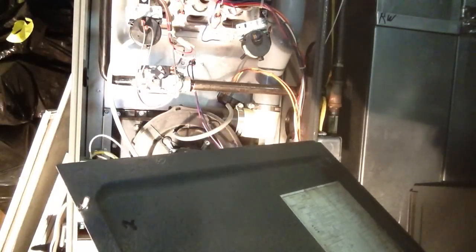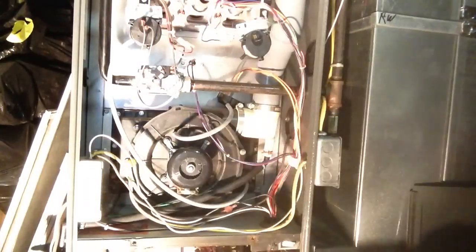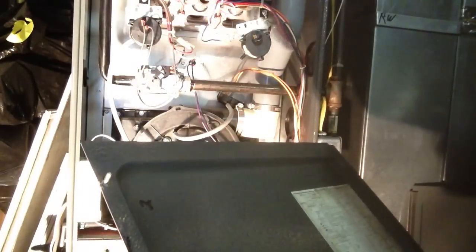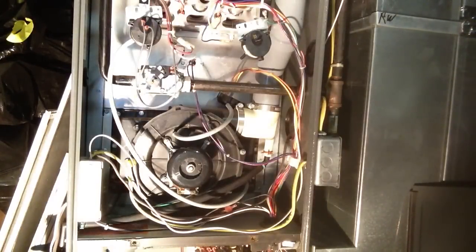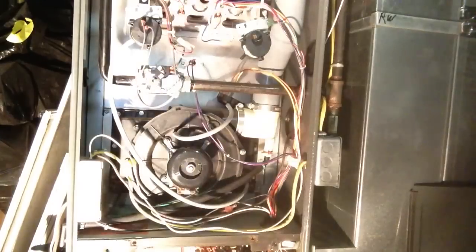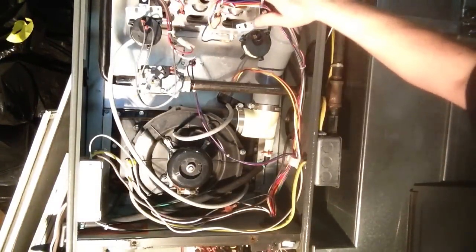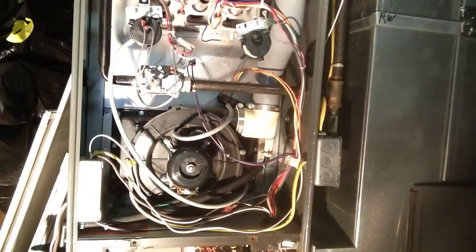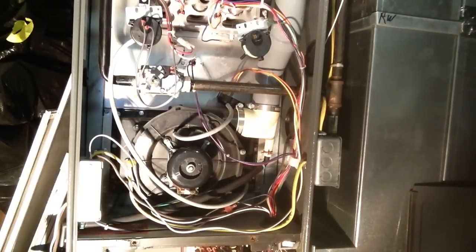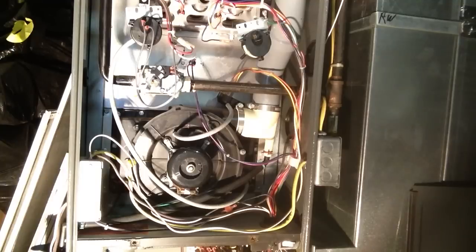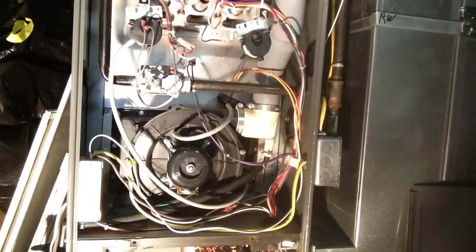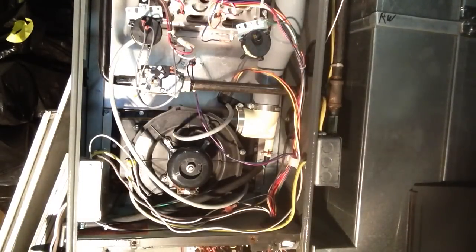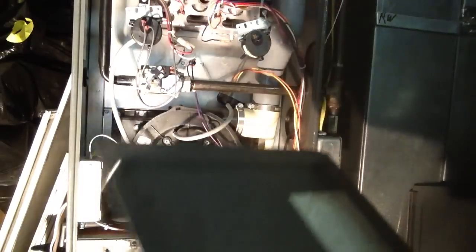Number five, flame sense without gas valve. I believe that is your flame sensed a flame, but the gas valve didn't open. I believe that's what that is. I've never had that code, but that's probably what I would look at. Flame sense without gas valve. I guess someone could heat that up and try and fake it out at the end to come on. I guess something like that could happen.